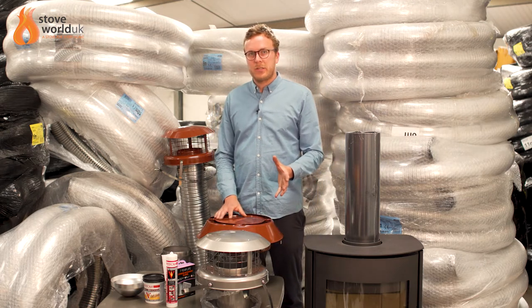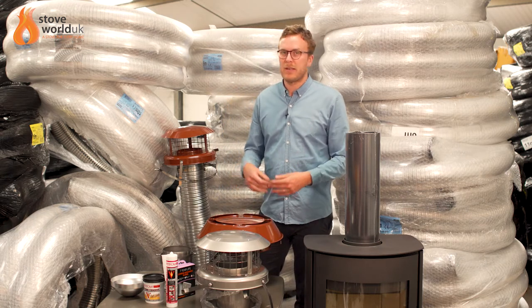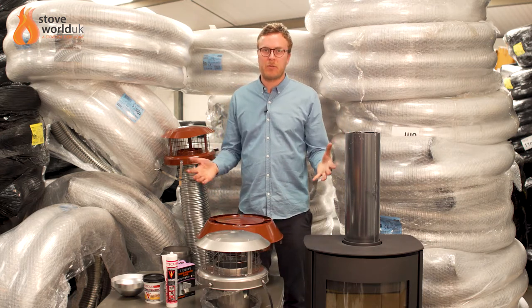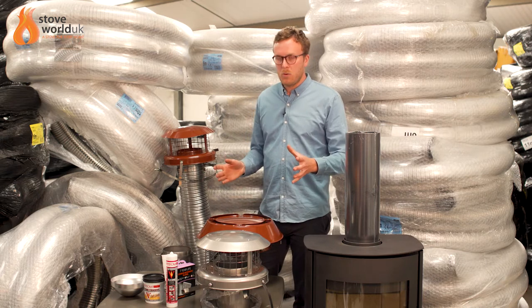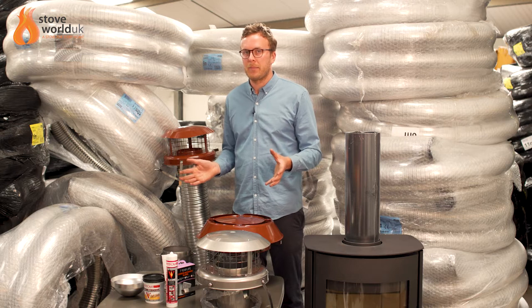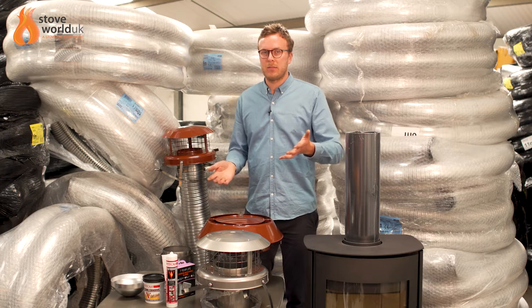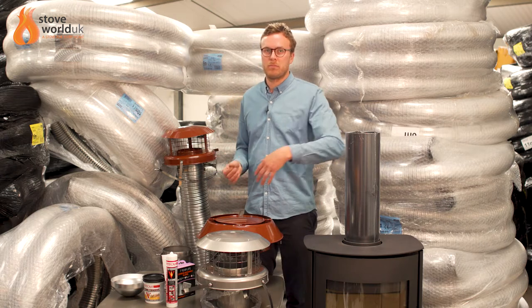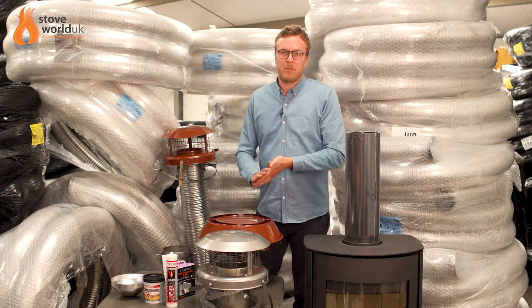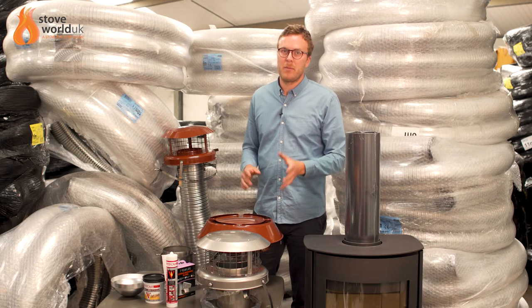The other question you need to ask yourself is what fuel you'll be burning. Most people will be burning wood with the occasional smokeless fuel. In that case you'll generally need a 316 grade liner. If you're going to be burning more smokeless fuel, you can upgrade to the higher grade 904 liner. Some people opt for the 904 anyway even though it's more expensive, but if you are just burning wood, the 316 grade is absolutely fine and will save you money.